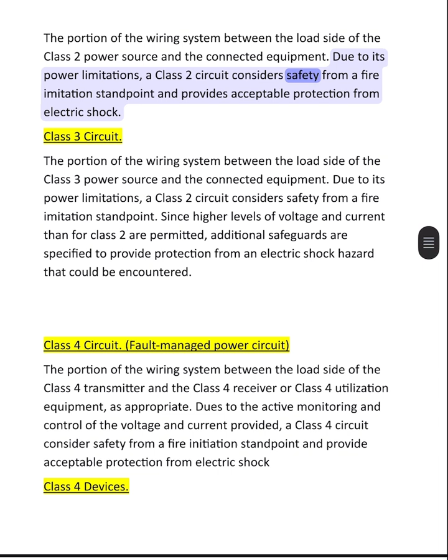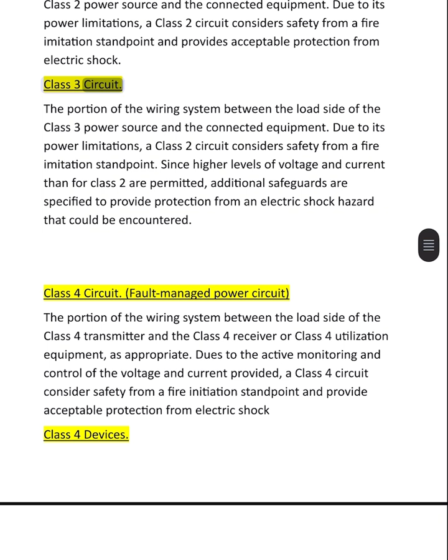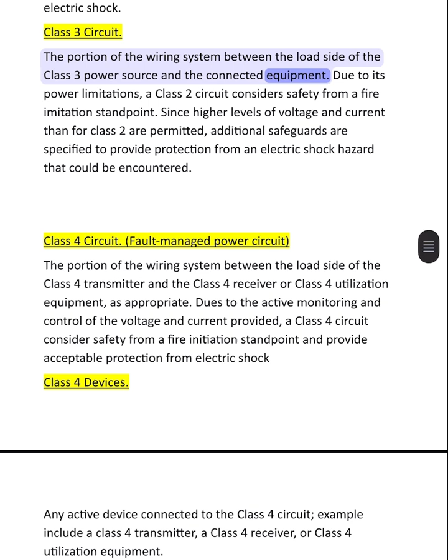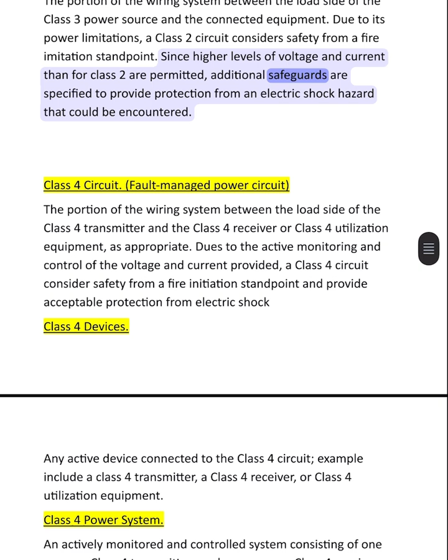Due to its power limitations, a Class 2 circuit considers safety from a fire initiation standpoint and provides acceptable protection from electric shock. Class 3 circuit. The portion of the wiring system between the load side of the Class 3 power source and the connected equipment. Due to its power limitations, a Class 3 circuit considers safety from a fire initiation standpoint. Since higher levels of voltage and current than for Class 2 are permitted, additional safeguards are specified to provide protection from an electric shock hazard that could be encountered.